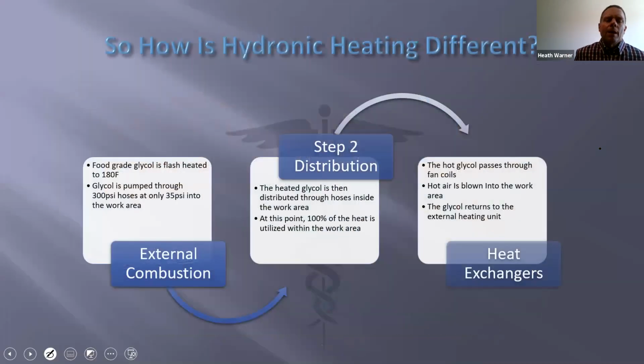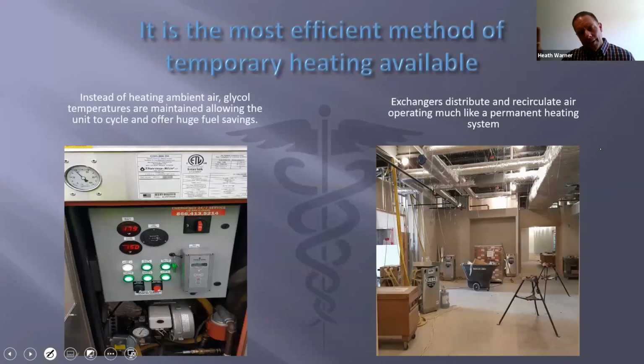The heating unit has glycol inside of it. What we're doing is we have a boiler, a temporary boiler. We're flash heating food grade glycol up to about 180 degrees, pumping that glycol through 300 PSI hoses, but only at 35 PSI. That heated glycol goes inside the work area, goes to those little boxes that you saw, where air can be blown through filters and continuously recirculated. The glycol goes back to the heating unit to be recycled and reheated.